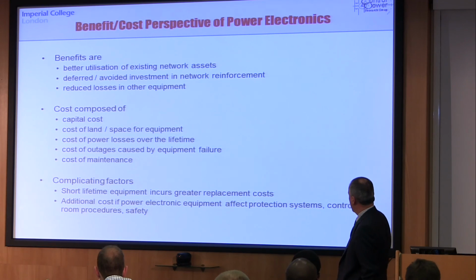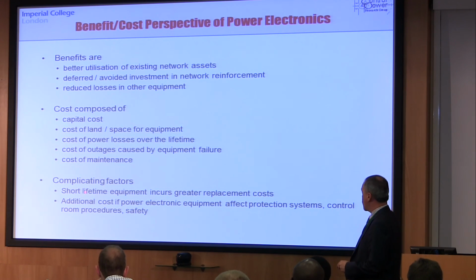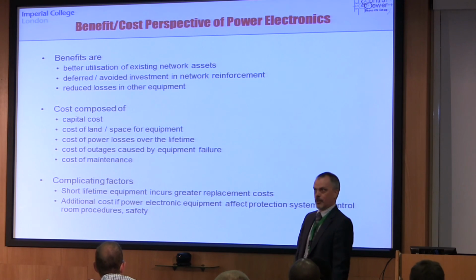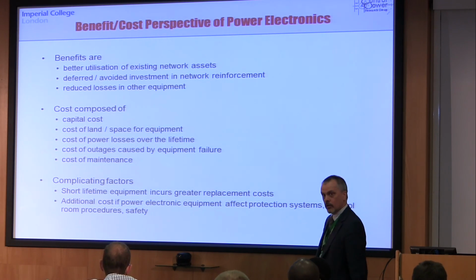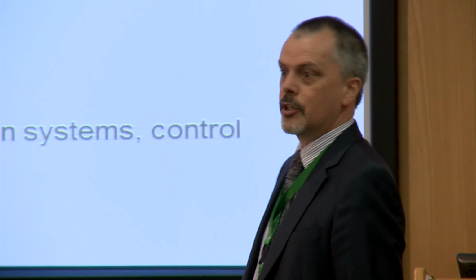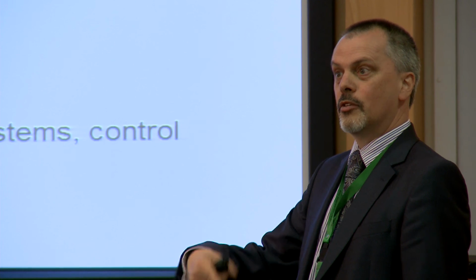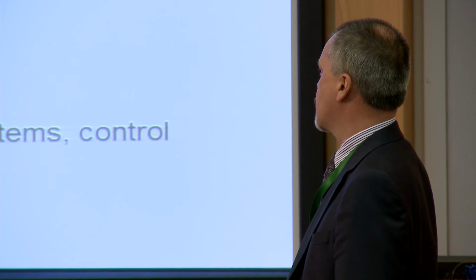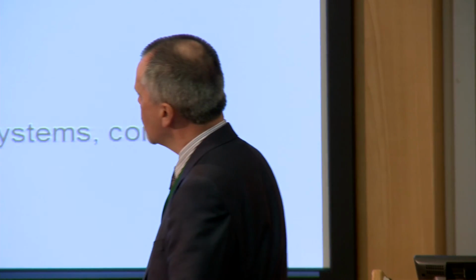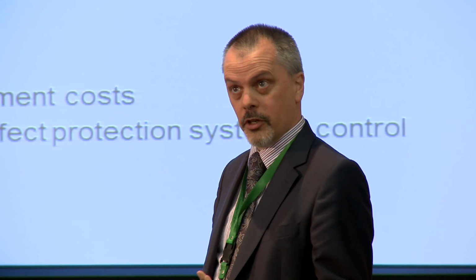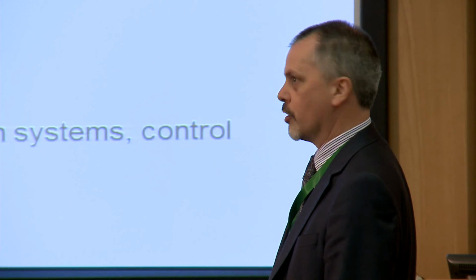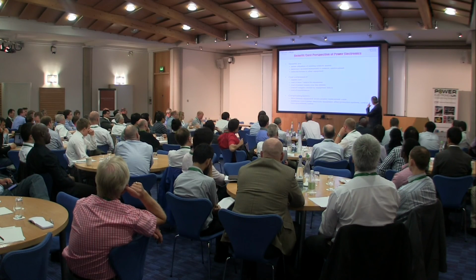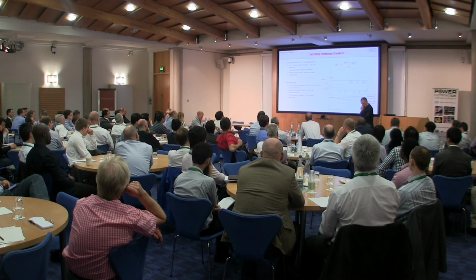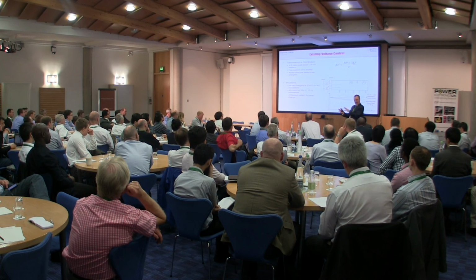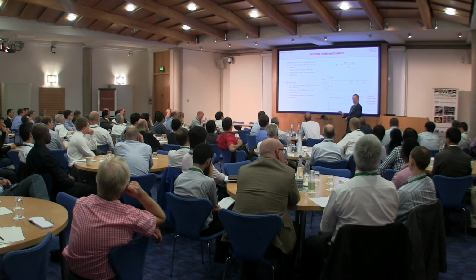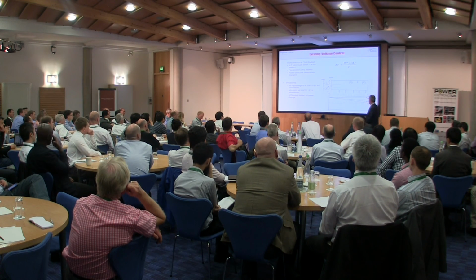And a couple of factors down the bottom here that I think are particularly important. Lifetime is an issue in cost because it's about replacement costs. And network assets at the moment have very long lifetimes, 30, 40, 50 years. Power electronics are probably on much shorter replacement cycles than that, and that affects your view of capital cost. And there may be additional costs when you put power electronic equipment in if you have to review protection and control systems and such. So, assuming that's what we've got to target, not just addressing the benefits, but keeping an eye on what we're doing about the costs as well.